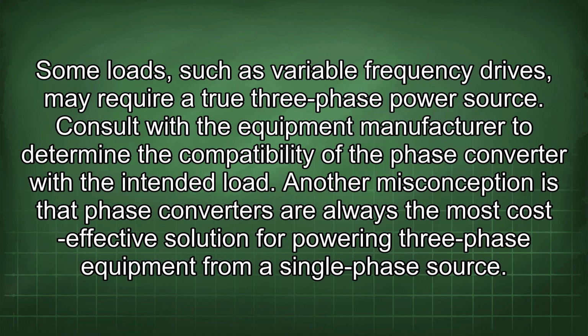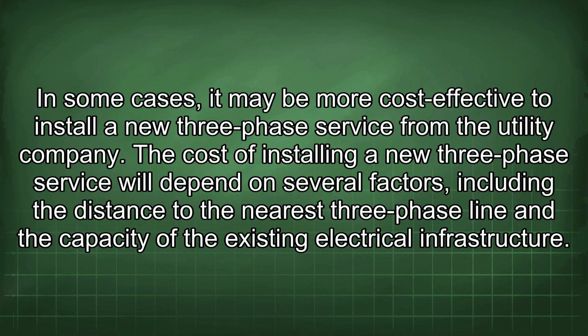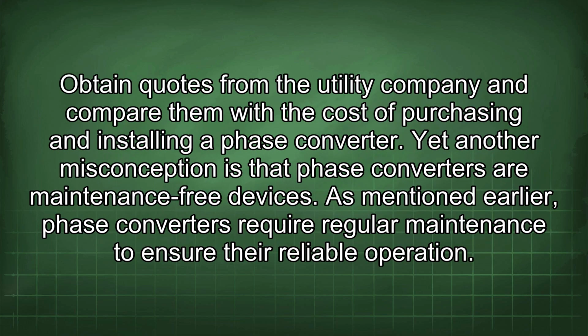Another misconception is that phase converters are always the most cost-effective solution for powering three-phase equipment from a single-phase source. In some cases, it may be more cost-effective to install a new three-phase service from the utility company. The cost of installing a new three-phase service will depend on several factors, including the distance to the nearest three-phase line and the capacity of the existing electrical infrastructure. Obtain quotes from the utility company and compare them with the cost of purchasing and installing a phase converter.